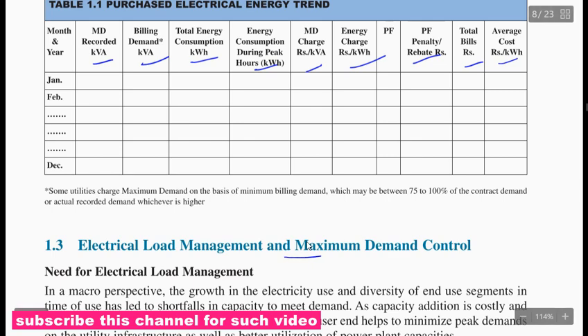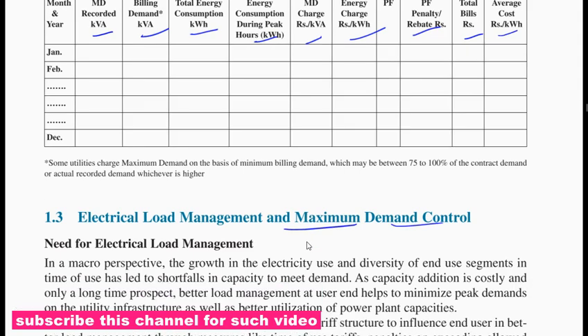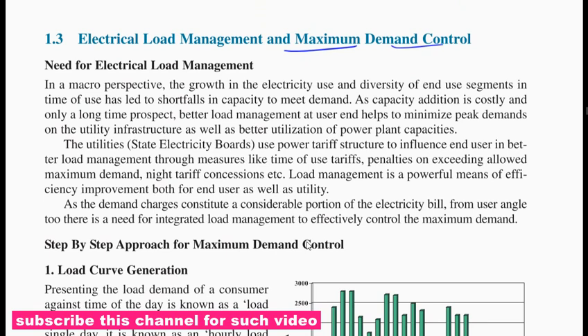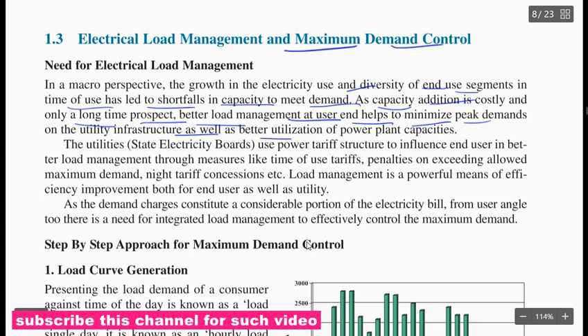Electrical load management and maximum demand control. Need for electrical load management. In a macro perspective, the growth of electricity use and diversity in end use segments and time of use has led to shortfalls in the capacity to meet demand. As capacity addition is costly and has only a long-term prospect, better load management at user ends helps to minimize the peak demand on the utility infrastructure as well as better utilization of power plant capacities.